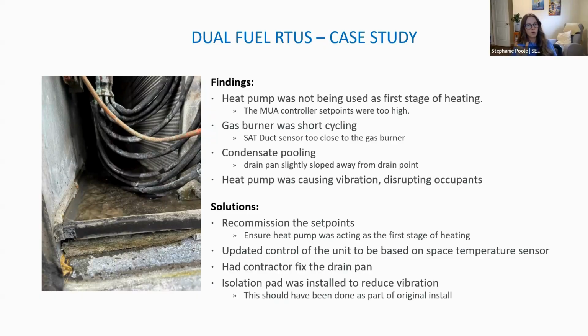But those set points are important to tweak and to look at, like, how is that switching over? Because we were seeing that the heat pump compressor was cycling and the gas burner was short cycling. This has to do with where the duct sensor was placed. It was actually too close to the heating. So the heating would turn on, and the sensor would be like, oh, I'm at 40 degrees, I'm way above set point, turn off. And then the cooling would come on, and it was a mess. And so it wasn't saving very much energy. It's really important to look at those and to tweak them. And on the next slide, I'll talk about how you can do that.